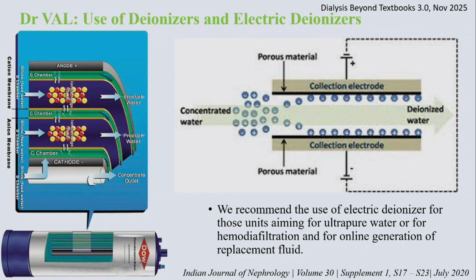I went to a unit, you were there with me on the occasion, where we found that the deionizer had not been regenerated for 7 months. And it was actually leaching magnesium into the water, and patients were getting hypermagnesemia on dialysis. But that's true of all these resin deionizers. If the resin is saturated, the property is that whatever it has collected, it will release it into the water. So you will actually make the water much worse than what it was. That's exactly what happened, and we published that in Haemodialysis International.